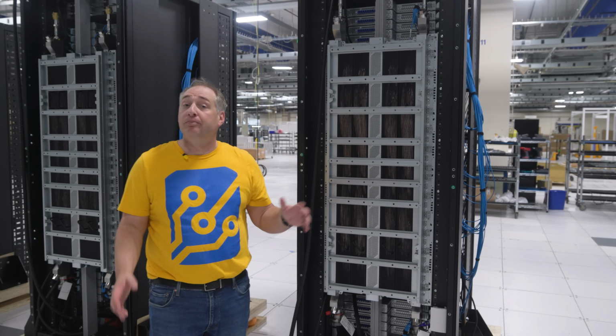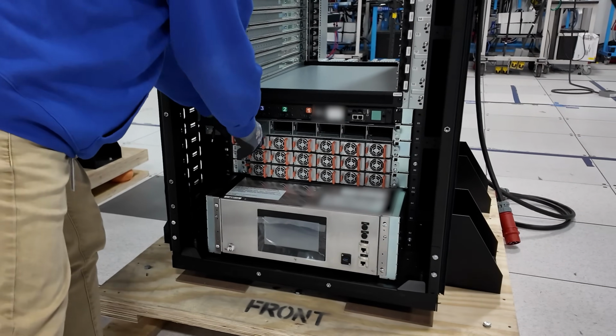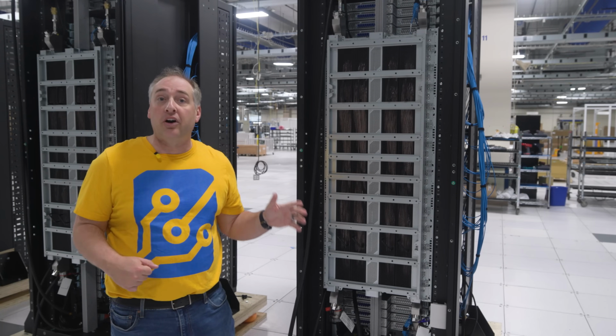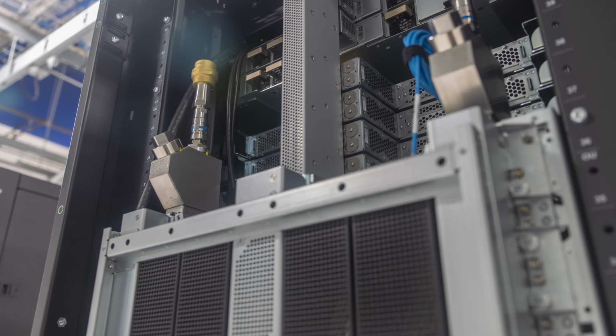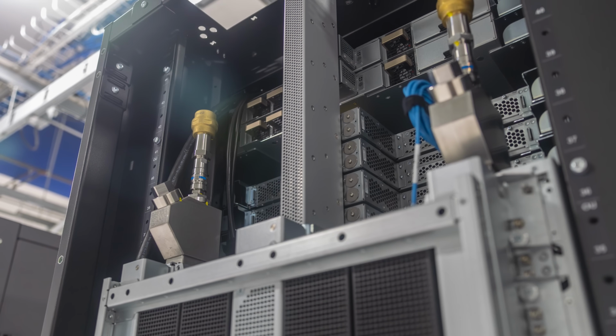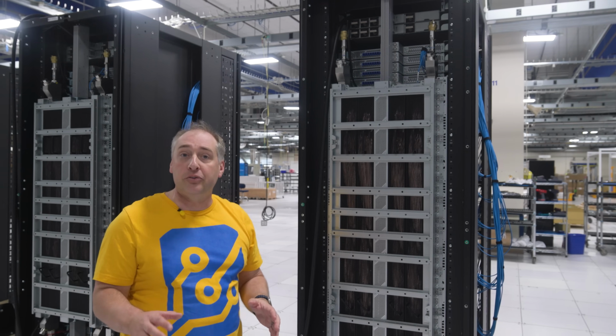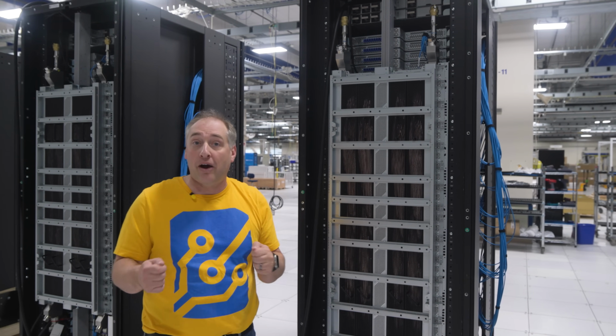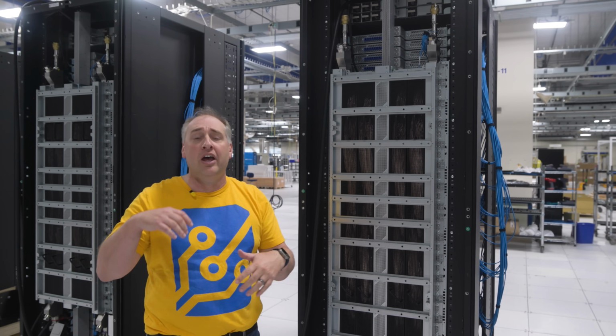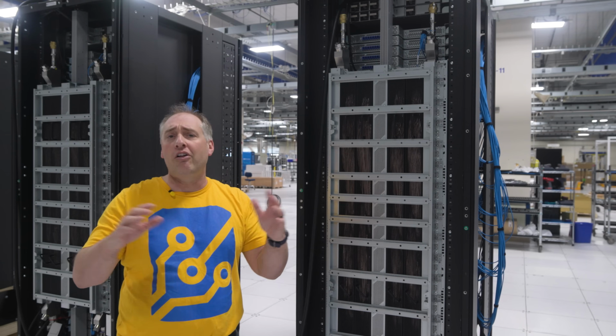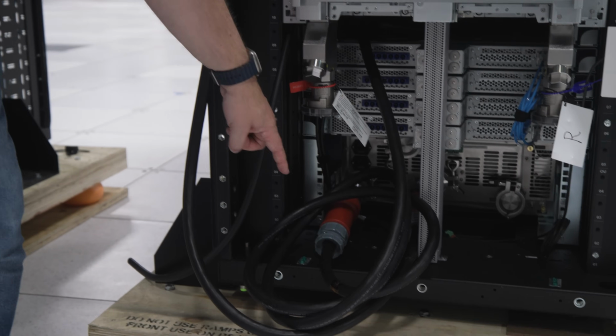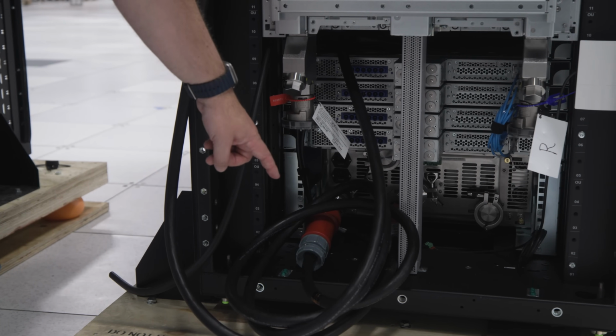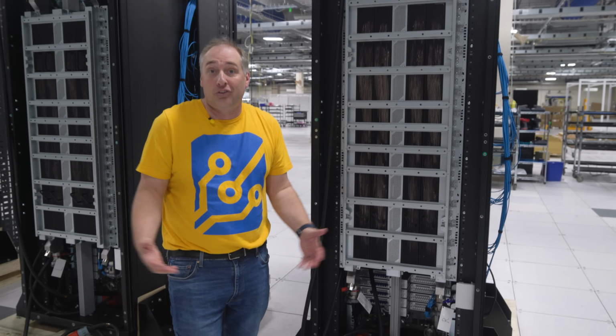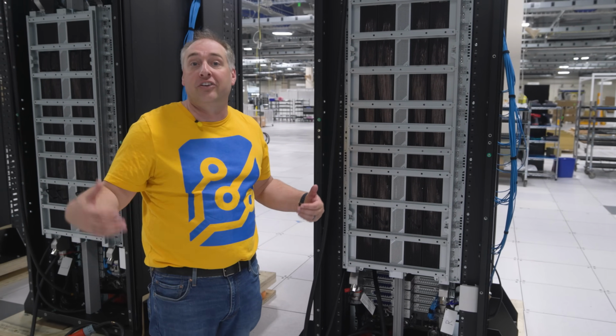And one other quick feature, you've seen the power shelves. When these get installed, they connect to the bus bar in the rear. You can kind of see the bus bar up here, but it goes all the way up and down the rack. Now, the importance of that bus bar is instead of having two power supplies in each of the compute nodes and the NVLink switches and all of those components, instead what you have is just these giant power connectors down here. And these giant power connectors, they're the only things that you need to connect to your facility electricity.